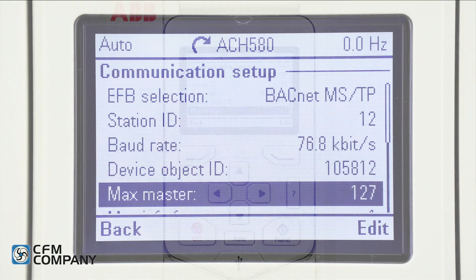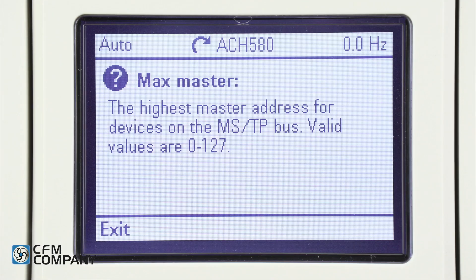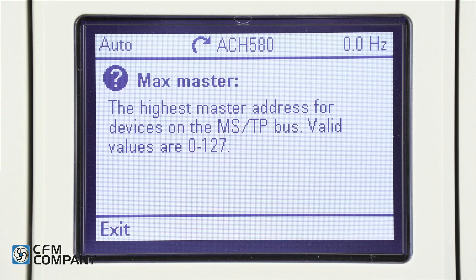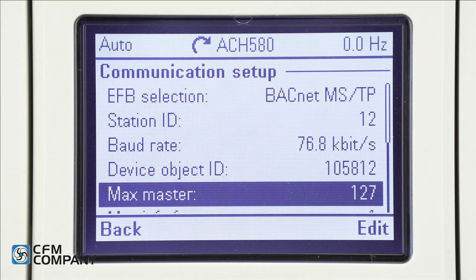Next is max master. Press the question mark button. This is the highest master address number of devices on the BACnet MSTP bus. Press exit. The default is 127 — leave this at the default for basic setup.